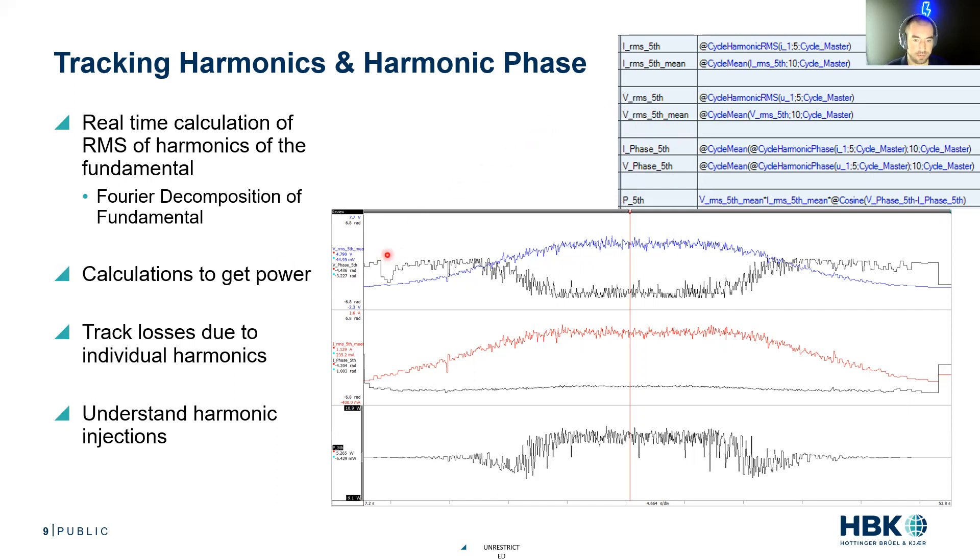I just multiply the RMS of the fifth harmonic times the current RMS of the fifth harmonic times the cosine of the difference of the phases. I'm actually calculating what is the power contribution of my fifth harmonic. This is really cool because this is all being executed in real time. We're seeing all of this as a scope trace. In my example, I have my fifth harmonic RMS in blue. For this given test, I was ramping up speed, holding a given speed, then ramping down speed, and I was holding a constant torque the whole time.